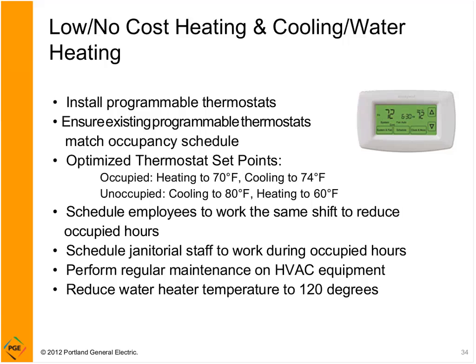And reduce water heater temperature to 120 degrees. Most offices and retail spaces really only have a bathroom sink or a few bathroom sinks and maybe a small lunchroom kitchen sink. You don't really have much of a water heating load there, and there's really no need to have the temperature set much more than 120 degrees.